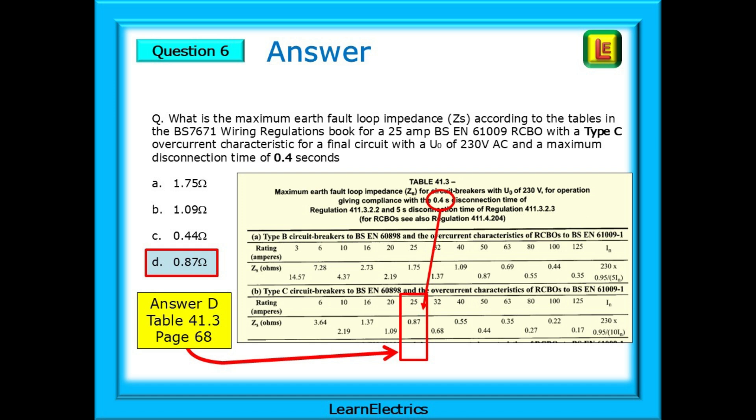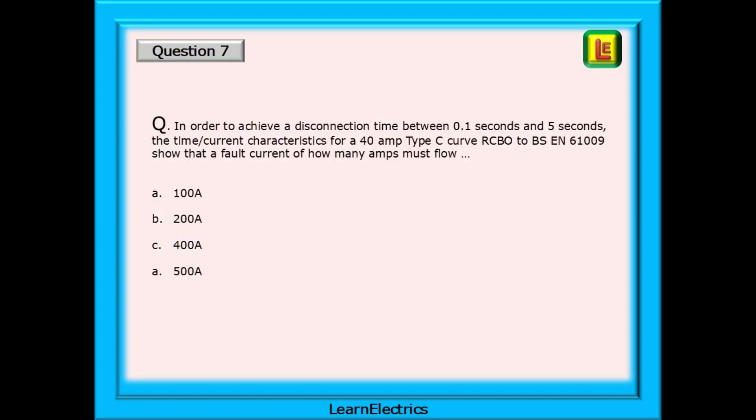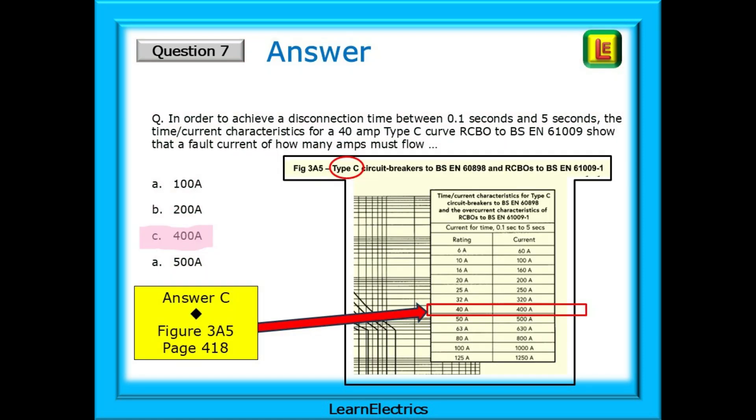For question 7, in order to achieve a disconnection time between 0.1 seconds and 5 seconds, the time current characteristics for a 40 amp type C curve RCBO to BS EN 61009 shows a fault current of how many amps must flow. This is answer C, 400 amps and is found in figure 3A5, on page 418.